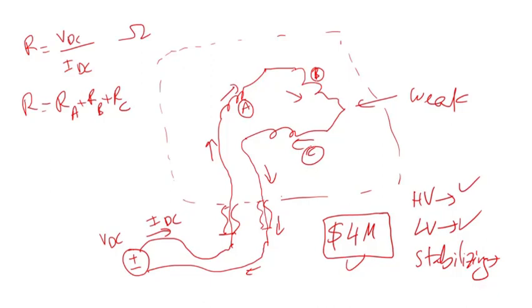So imagine $4 million and no test is done to check. If you bring out at least one bushing, you can do winding insulation resistance and insulation power factor tests. If you bring out 2 bushings, you can add another test, which is winding resistance. So at least there is some kind of checking to make sure that this winding is designed properly.